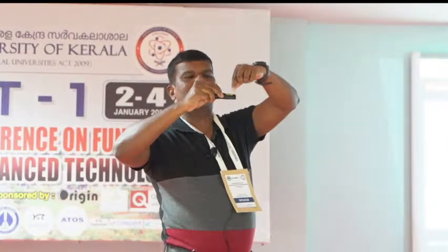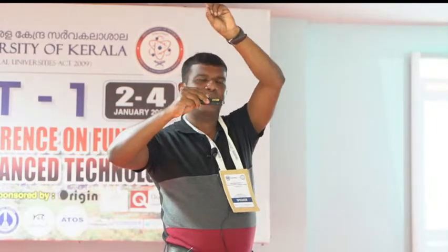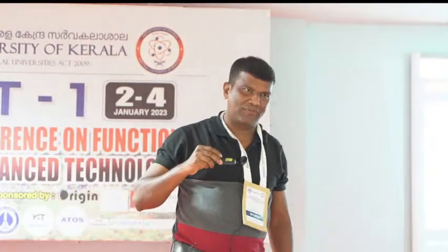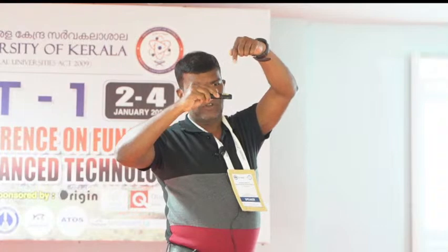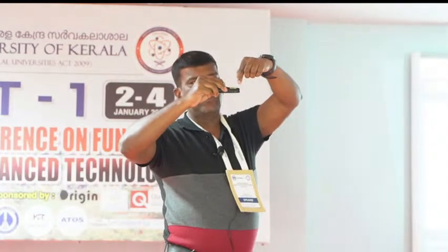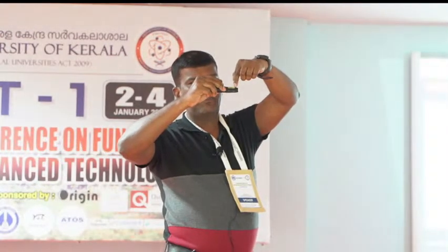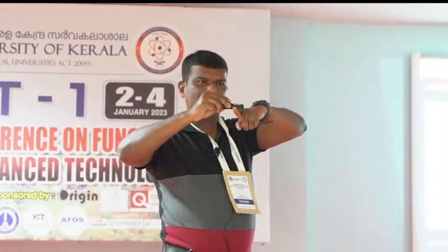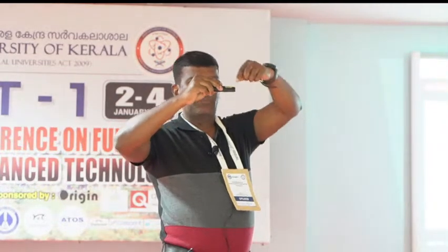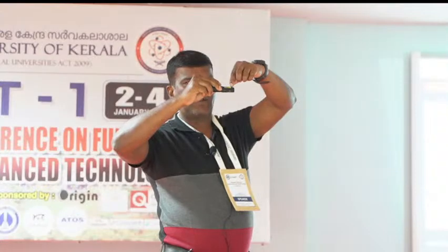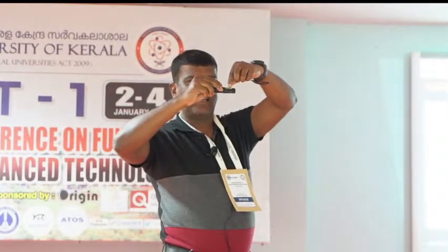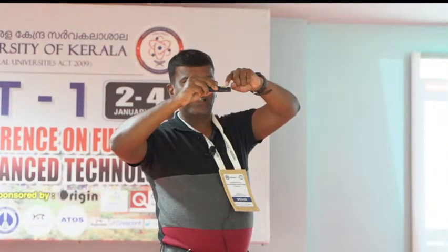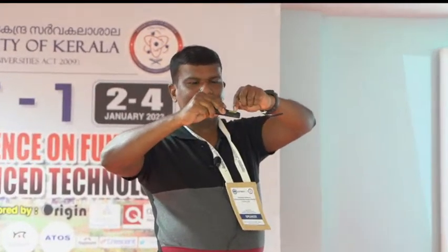What it will show you is the electrostatic curve, which probably looks like a butterfly loop, but that is not the actual PFM butterfly. That is actually the electrostatic butterfly. So you don't need that. Normally when you want to perform your PFM measurements, you need to have a very good contact between tip and sample. So if you move your laser from the end to slightly inside, this position has to touch the substrate because the detector will think that the laser is here.